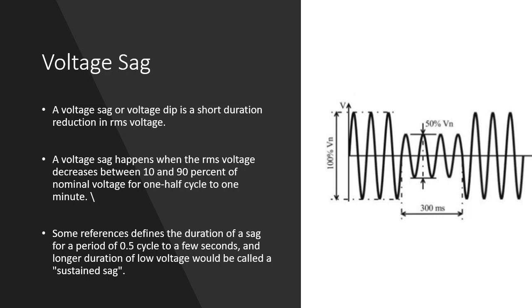What is voltage sag? Voltage sag is a sudden dip in the nominal voltage. This figure represents voltage sag. My nominal voltage is V-nominal, and at some time t equal to zero, my voltage faces a dip or drop in its amplitude, which is between 0.1 to 0.9 per unit, or from 10% to 90%. In this figure I have a 50% drop in my voltage from the nominal value.